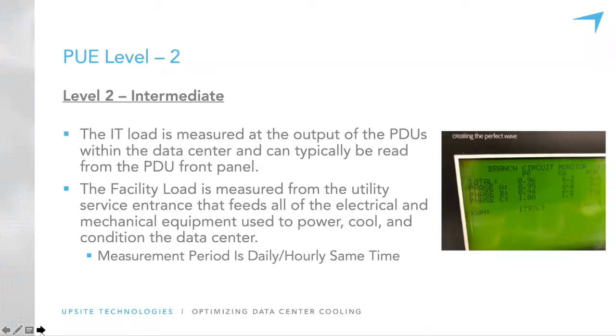One of the things that I do on a weekly basis when I'm measuring PUE is I will actually go to the floor PDUs. I know the makeup of our floor PDUs. I know which UPS system they're tied to, and I try and do a check and balance to say, okay, this is what I'm reading here. Is it matching or fairly close on the UPS? It might not always be exact because of the power factor associated with the UPS system, but should be really close in what I'm seeing from the floor PDU to the UPS system.